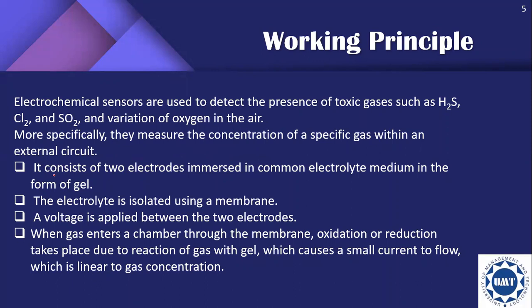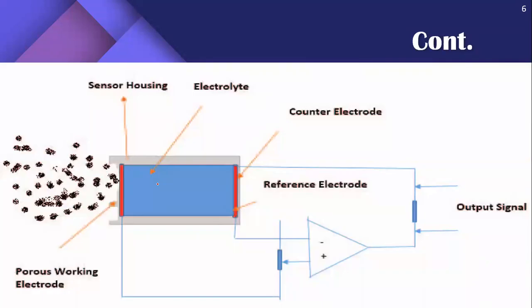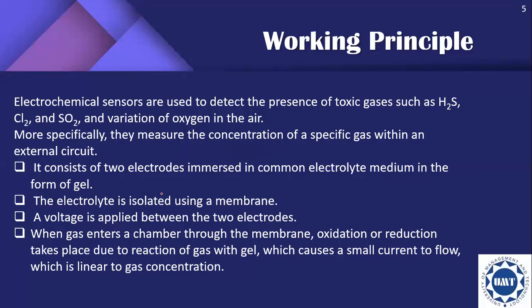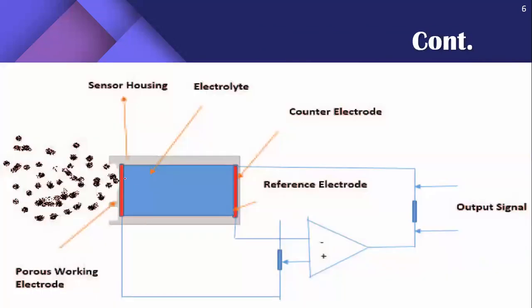The operation of an electrochemical sensor consists of two electrodes. These two electrodes are immersed in a common electrolyte medium in the form of a gel. The electrolyte is isolated using a membrane.